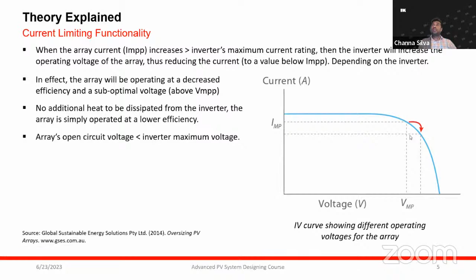And if the inverter allows, yes, of course you can have much more, where your maximum power point operating current can exceed even the inverter's maximum current rating. If you look at this particular example, they rated a 5 kilowatt inverter with strings of 2.4 kilowatts each, and for the first string there won't be any power loss. Red color represents the inverter losses, and the blue color represents the system production. If connected with two strings, the losses are still very minimal, because that 5 kilowatt inverter is connected with a 4.8 kilowatt DC array. If it is three strings, then it reaches 7.2, which is oversizing by close to 45%. In that case, loss will be higher.